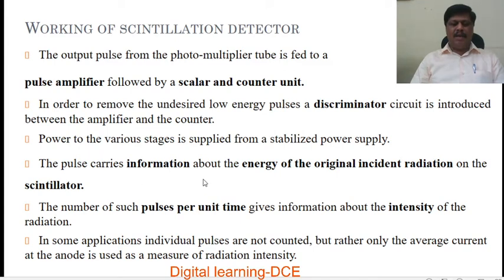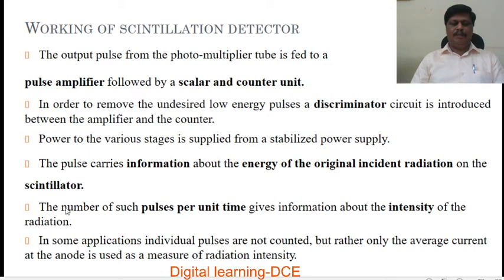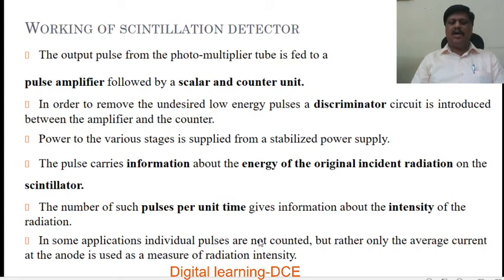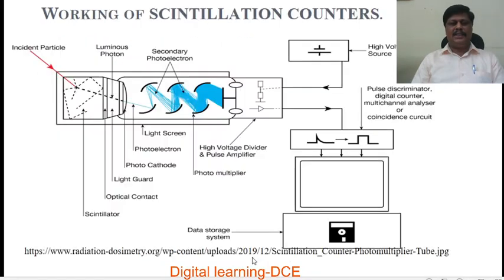The pulse carries information about the energy of the original incident radiation on the scintillator. The number of such pulses per unit time — that is, the count rate — gives information about the intensity of the radiation. Intensity of radiation is directly proportional to pulses per unit time or count rate. In some applications, individual pulses are not counted, but rather only the average current at the anode is used as a measure of radiation intensity.